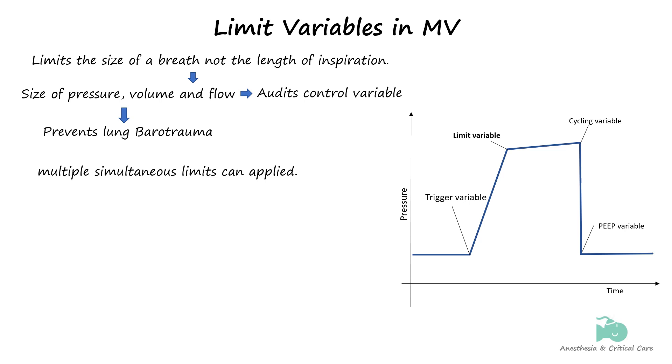That is not to say that those parameters are completely ignored during the other phases of ventilation. There are still limits in place, but they fall into the territory of safety parameters or alarm limit settings. For this reason, limit variables are preferentially called target variables now.